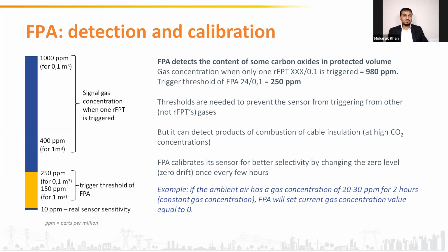Secondly, if for some reason somebody did not attend the alarm, or the gas escaped and the alarm is still there and a fire occurs, maybe in places where rFPTs are not installed, the fire will generate CO2. The FPA sensor can also detect a high concentration of CO2. Then also it will give an alarm. So this is the additional advantage we get with the presence of the sensors. Then FPA does not require any external calibration. It calibrates itself every few hours.